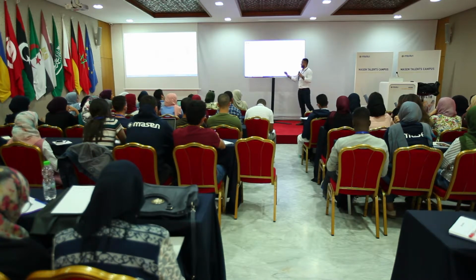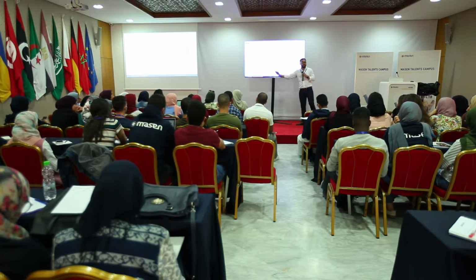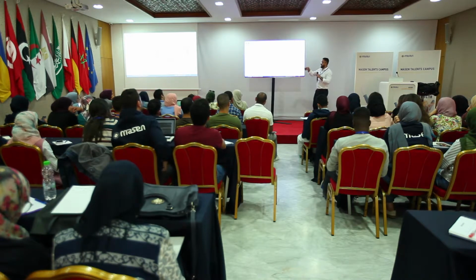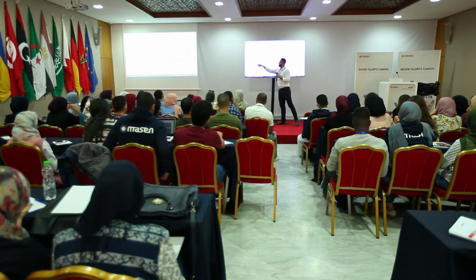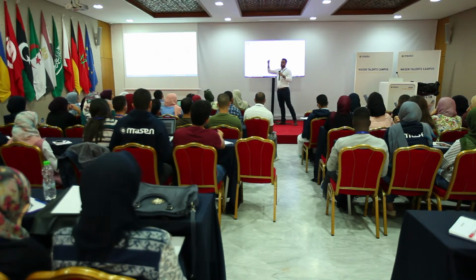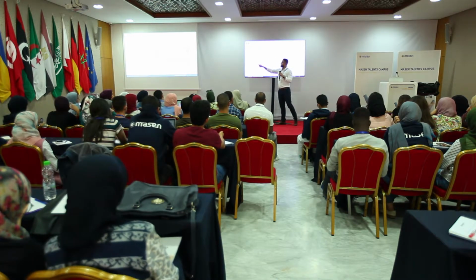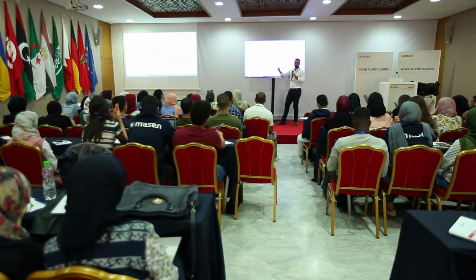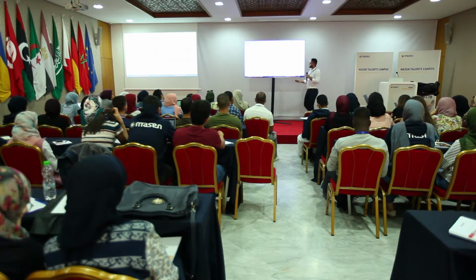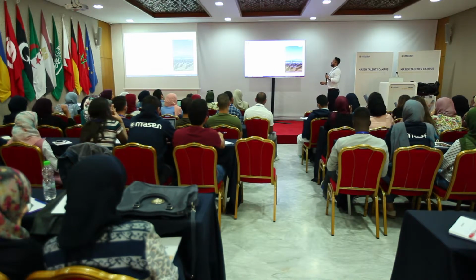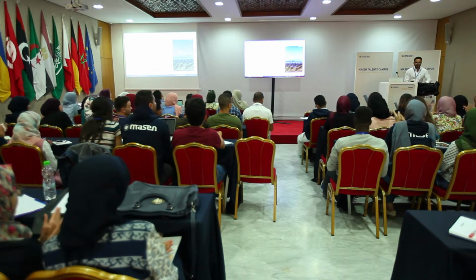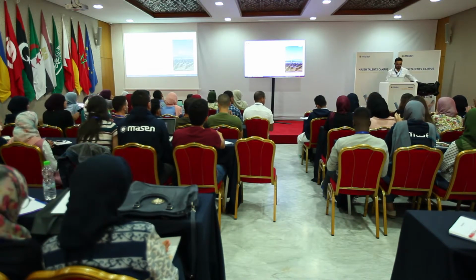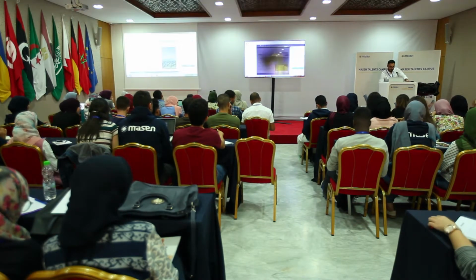So the solar multiple, and forget about this equation, it's just the ratio between the power required at the receiver to operate the power block at nominal conditions and the power collected. So if a power block, for instance, of 100 megawatt electric has a thermal efficiency, give or take, if it's a steam cycle, of 40%, then it requires a thermal power of, do the math, 100 divided by 40%, 250, whatever.